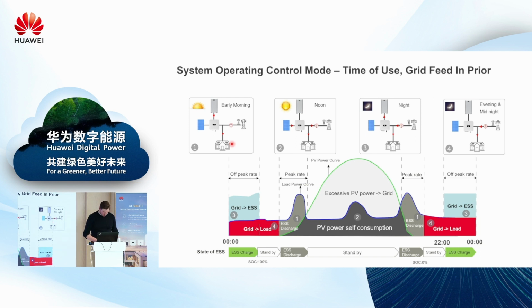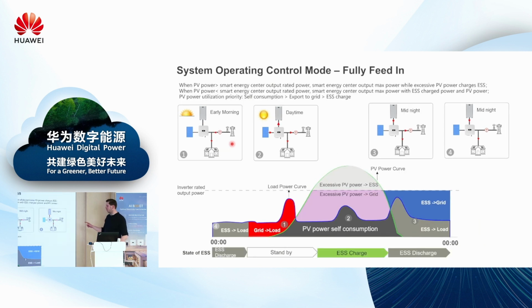There is also one very important, I would say huge, advantage of having a DC coupled system: you shouldn't be afraid of oversizing your PV installation when having the ESS. Because the line here is the maximum output power of the inverter.